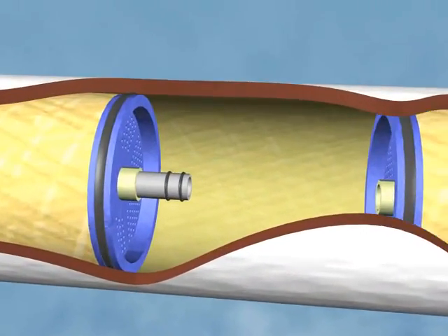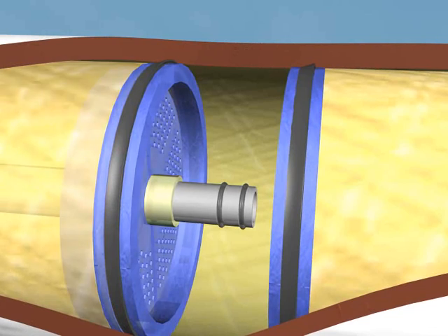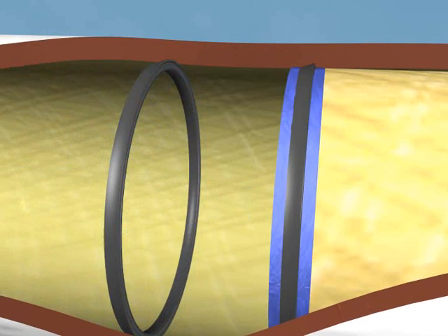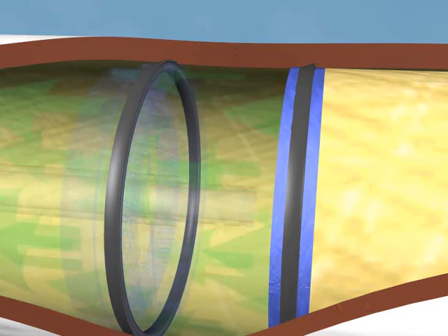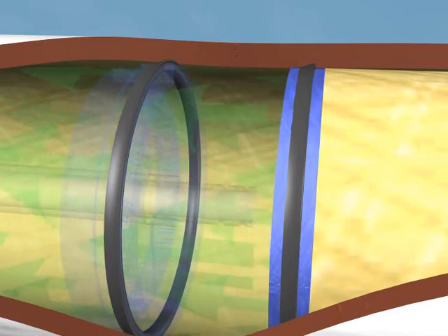Each element has a brine seal placed in the groove located on the outside of the anti-telescoping cap. It is critical that this brine seal always be placed on the feed water inlet side of the element and that the seal open in the direction of the feed water. This seal prevents feed water from going around the element rather than through it.